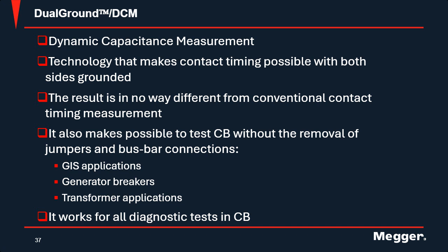So dual grounding with DCM, dynamic capacitive measurement. This technology makes contact timing possible with both sides grounded. It is also in no way different than conventional contact timing. You will not see a difference. It also makes it possible to test circuit breakers where removal of the jumpers or bus bar connections is difficult or time consuming, such as GIS applications. They have individual grounds that are hardwired in. You'd have to lift those and it's time consuming. With DCM, you don't have to lift those grounds.